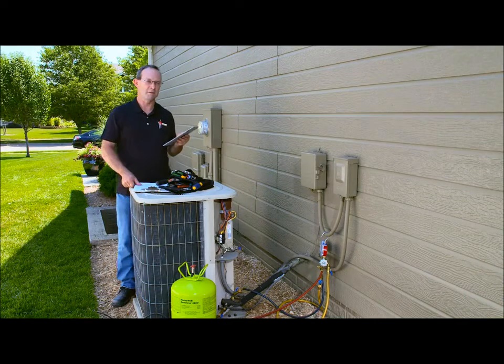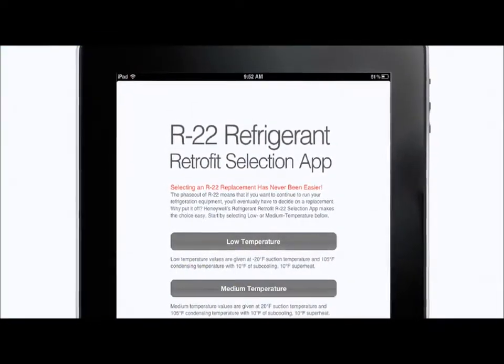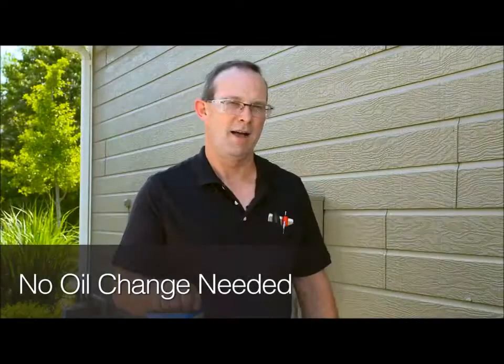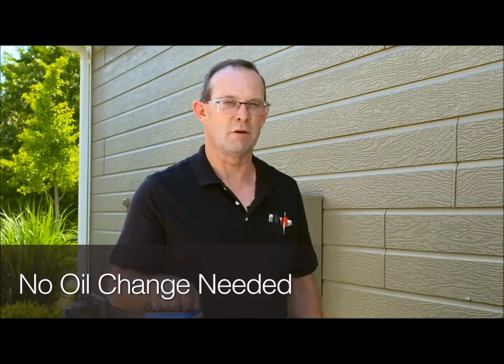Systems being charged with Genetron R422D use slightly less refrigerant than the R22 charge. This system holds about 6 pounds, so I'm going to multiply that by 0.95 to get my approximate R422D charge. Or I could use the Honeywell R22 retrofit app to do the calculation for me. On a typical air conditioning system with short lines, you won't need to make any changes or modifications to the mineral oil in the system.